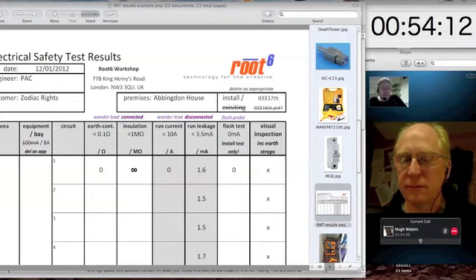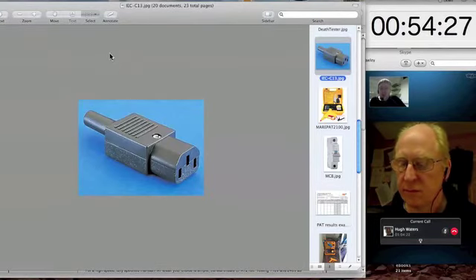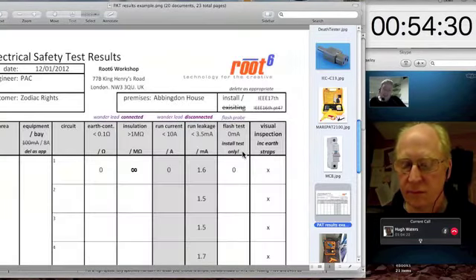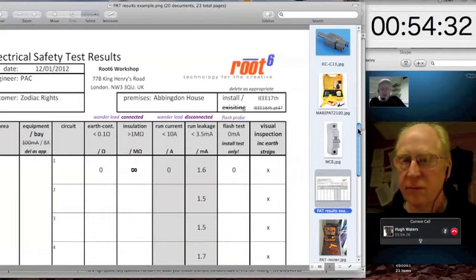So that's the next thing we measure and record. The next test that the PAT tester does is a run current test, on a single circuit within a bay, on a single IEC C13 outlet, that should be less than 10 amps. And in fact, when we're testing bays, invariably the equipment hasn't been delivered.